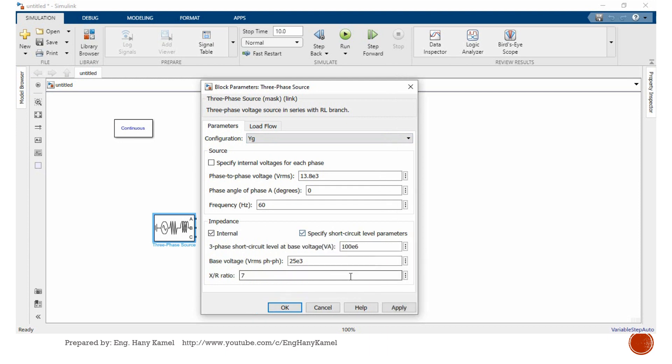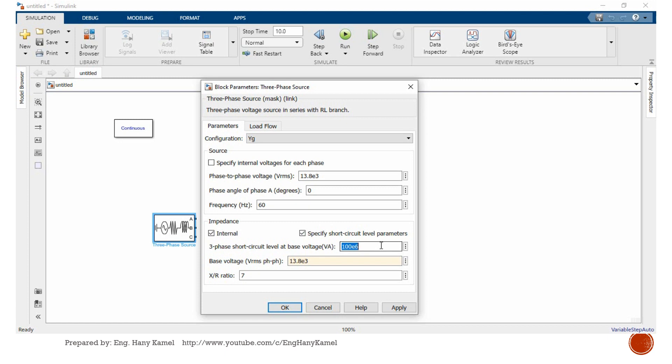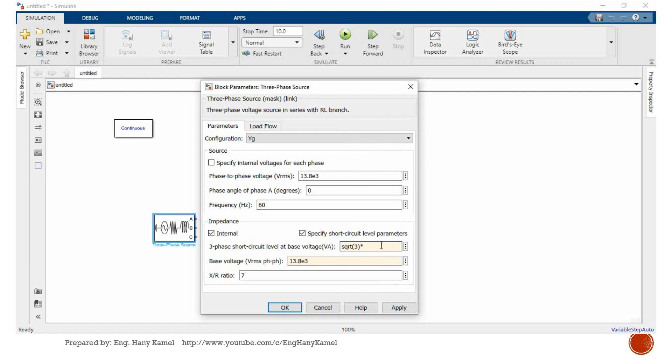Specify short circuit. Just for now, we will enter only 13.8 kV. X over R ratio, if you have this parameter you will enter it. Three-phase short circuit level, for example, we can enter square root of 3, times 13.8 kV, multiply by, let's say short circuit level is 25 kA.